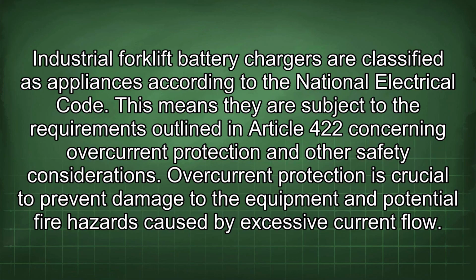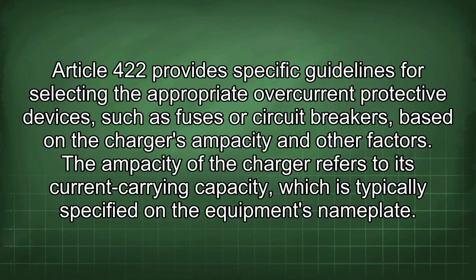Industrial forklift battery chargers are classified as appliances according to the National Electrical Code. This means they are subject to the requirements outlined in Article 422 concerning overcurrent protection and other safety considerations. Overcurrent protection is crucial to prevent damage to the equipment and potential fire hazards caused by excessive current flow. Article 422 provides specific guidelines for selecting the appropriate overcurrent protective devices, such as fuses or circuit breakers, based on the charger's ampacity and other factors. The ampacity of the charger refers to its current carrying capacity, which is typically specified on the equipment's nameplate.